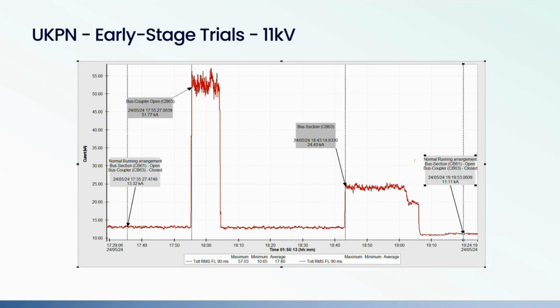I want to stress up front, it's not about the absolute values at the start of this graph, but what matters is the operational insight that we gained and how that informed our unit settings, configuration, and wiring as we went through the project. So under the normal running arrangement, the fault level settled at 13.3 kA, which was broadly what our operational team expected from the site.